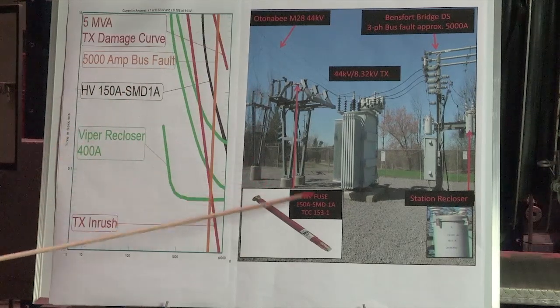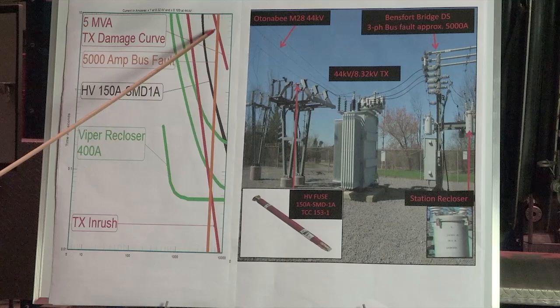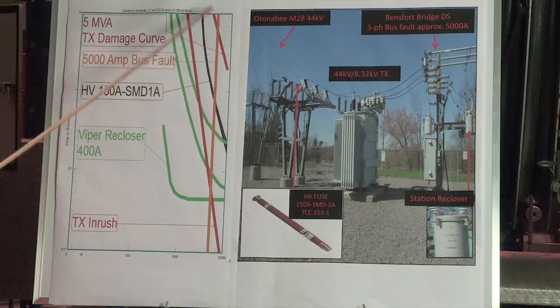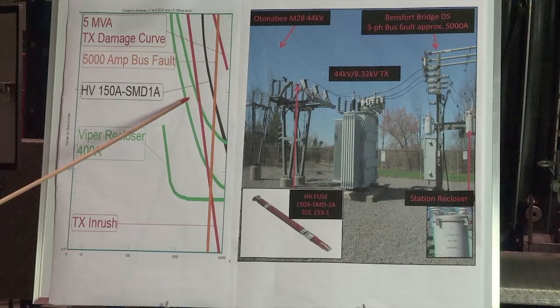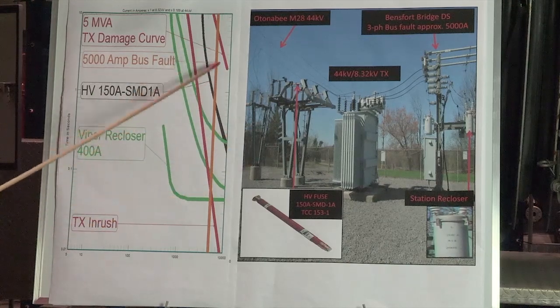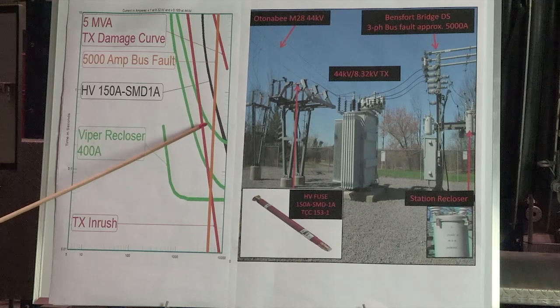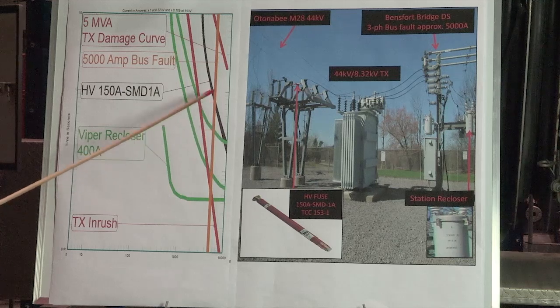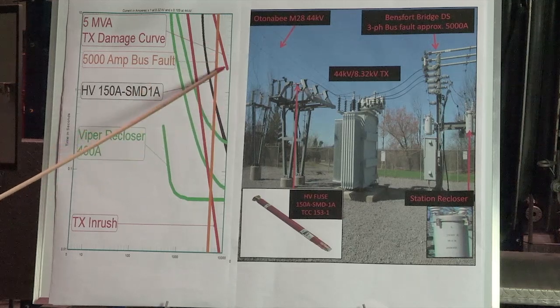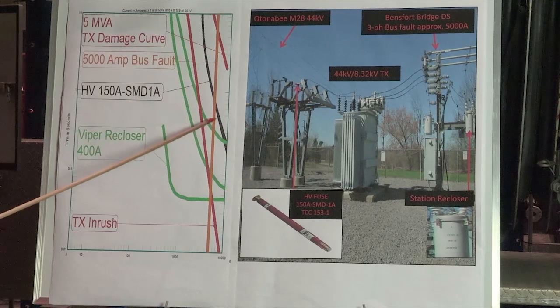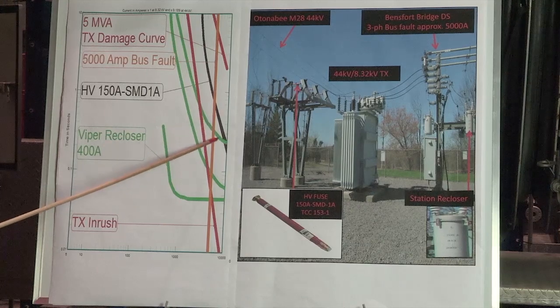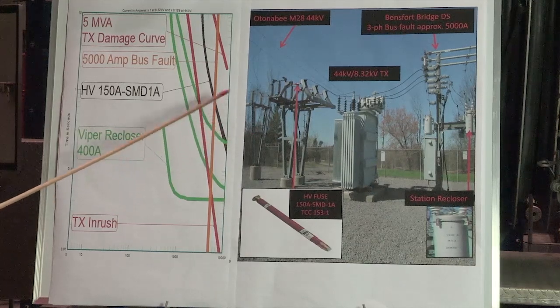So this next diagram here is basically showing everything that we've modeled in so far, from the transformer to the high side fuse to the recloser settings. So everything needs to have its own order as far as coordination is concerned. You can visually see that the recloser is going to clear the fault before the high side fuse, before transformer damage occurs. But these time differences are within milliseconds, and we do have standards as far as how many milliseconds before each device, because each device is going to require a certain amount of time to do its thing and trip and let the next device take care of it as well.